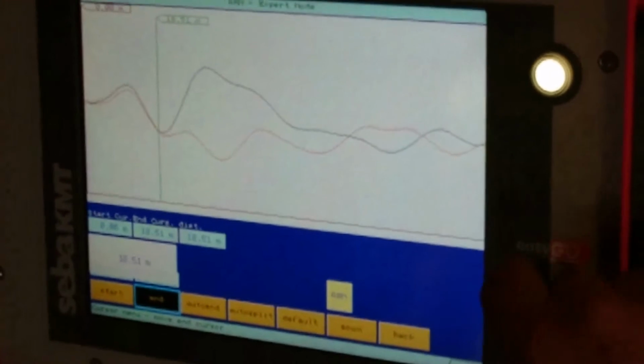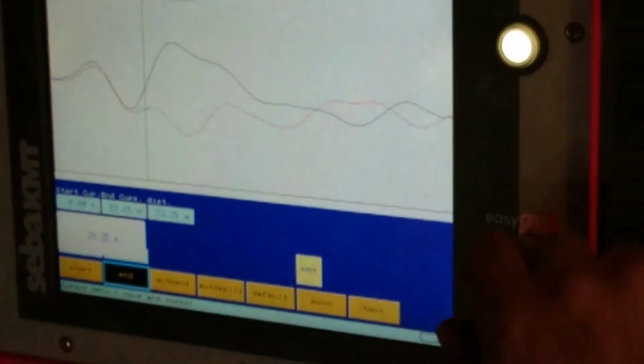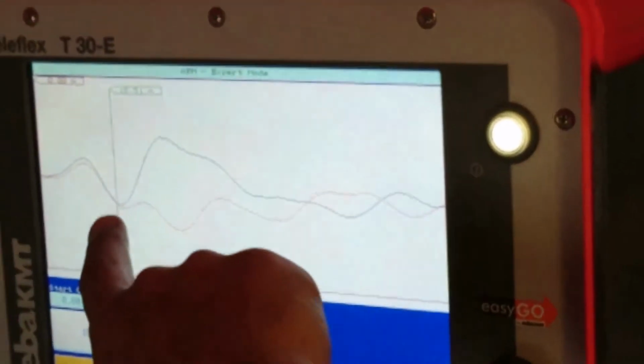Then you have to judge where the fault is yourself. How to do it? I'll just go to end cursor, select end cursor. See, now I can select where the fault is. How to judge? It's automatically picked up here somewhere around 18 meters. But this will help me a lot.